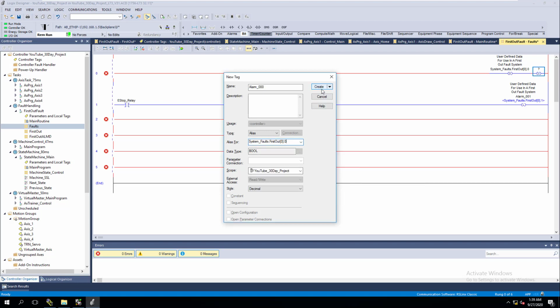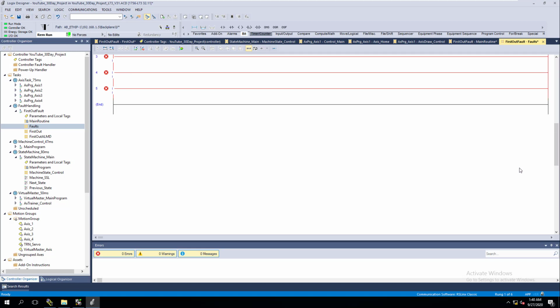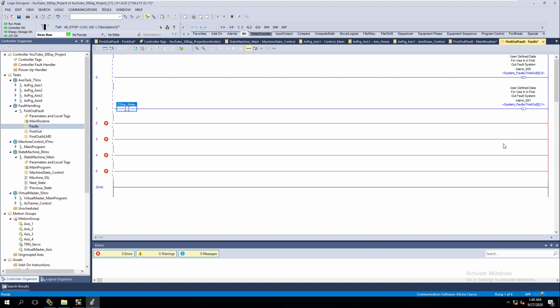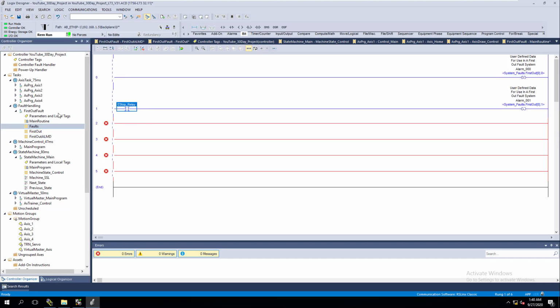Now we're going to do these, and you can imagine this can get pretty drawn out and daunting, because you're going to do these for every single fault you have in here. And for those faults you don't have, you're going to put them in anyway, and then just AFI them out. So you would have them for all 480 bits and then AFI them out. For our instance, we don't really need that. We do have a fault, and we have ALMDs that we could use, but let's go ahead and just show the fault working.